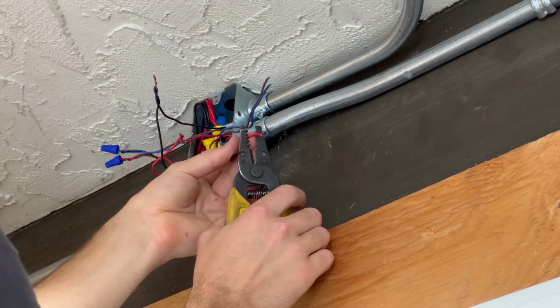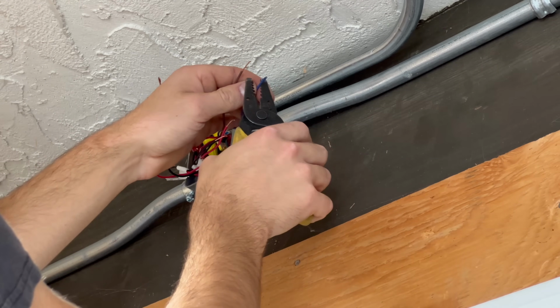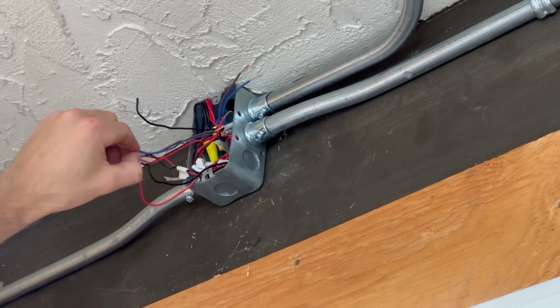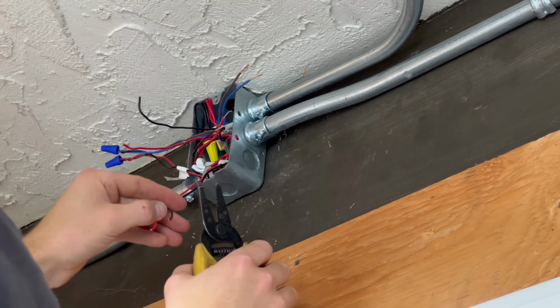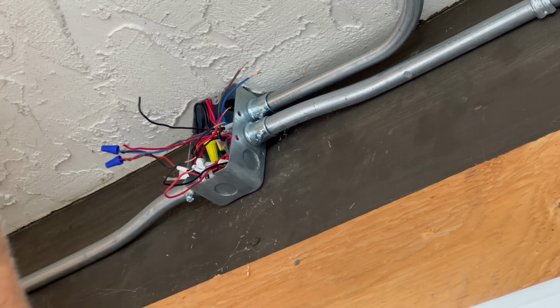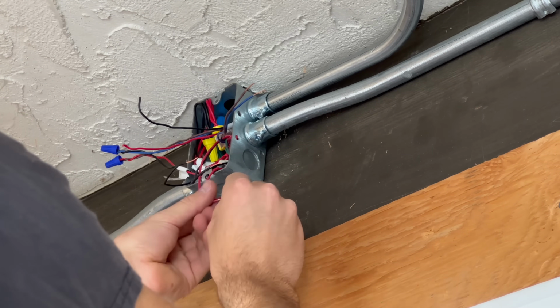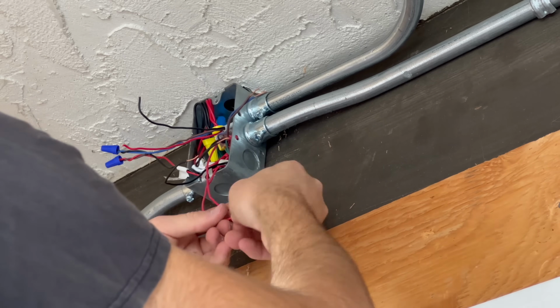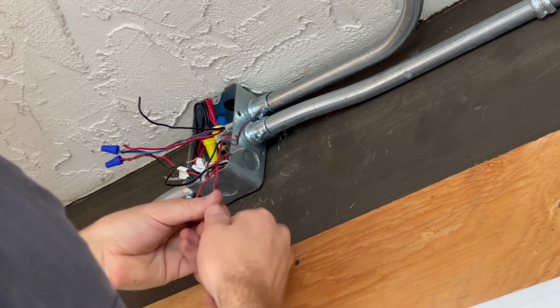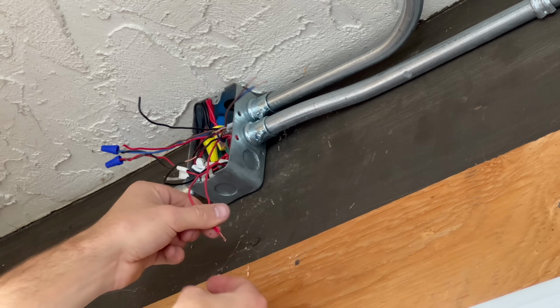So we'll prepare our new wires going down to the pull station first to minimize the amount of time we are in trouble. And now we'll get troubles. So this is our SLC in. I don't bother twisting this small 18. It usually holds together pretty good without pre-twisting. Larger conductors I will pre-twist though, 14 and bigger usually. So this is our SLC in getting spliced to the supply side of our pull station. There you can see, without pre-twisting, this small wire twists together pretty good.